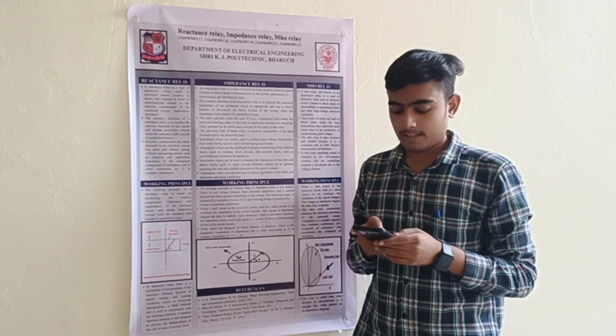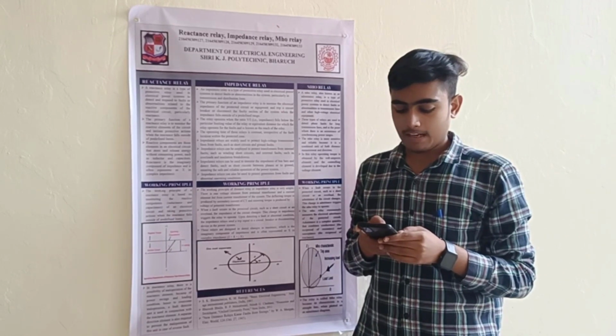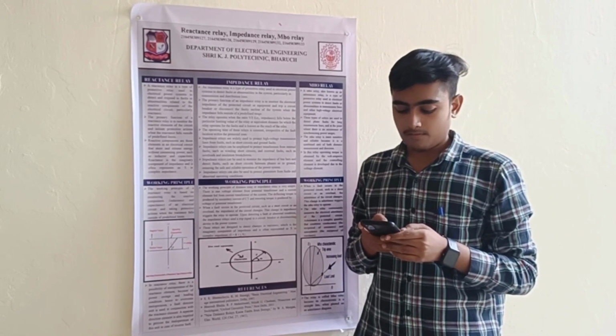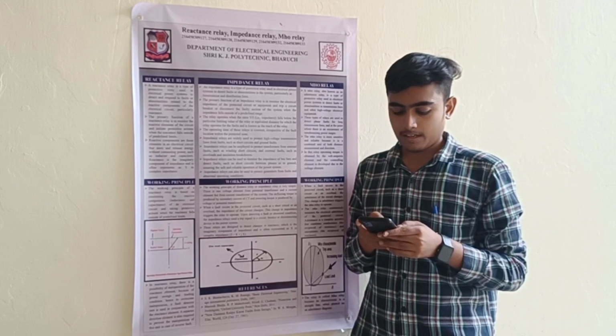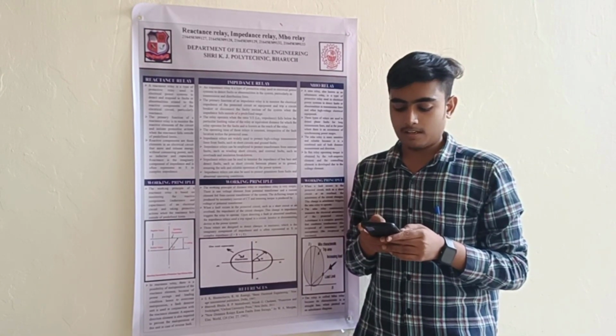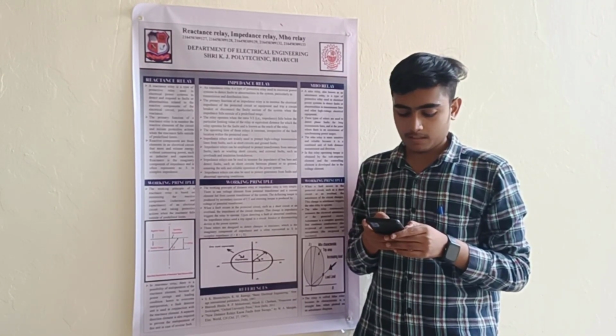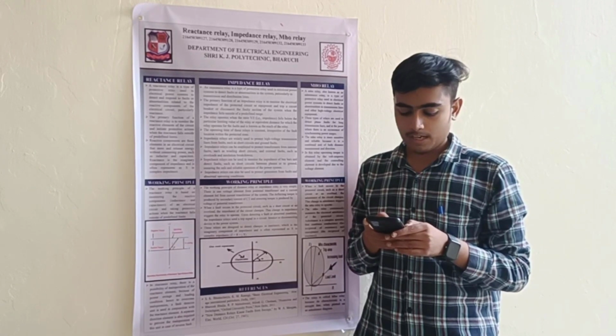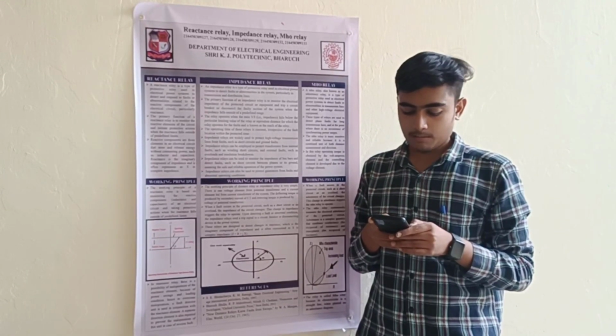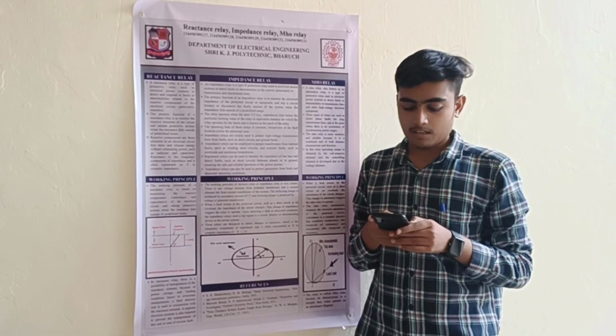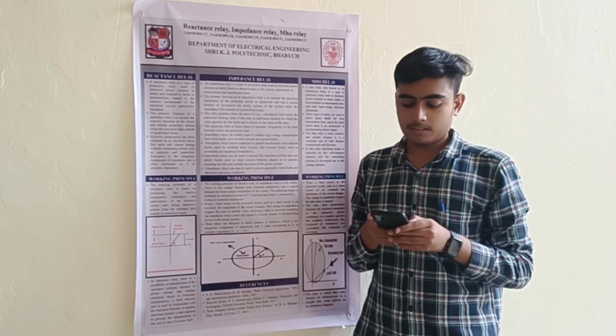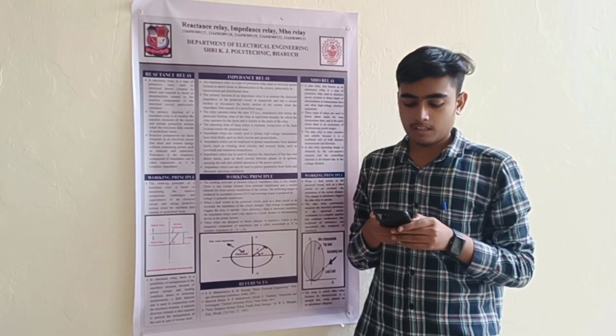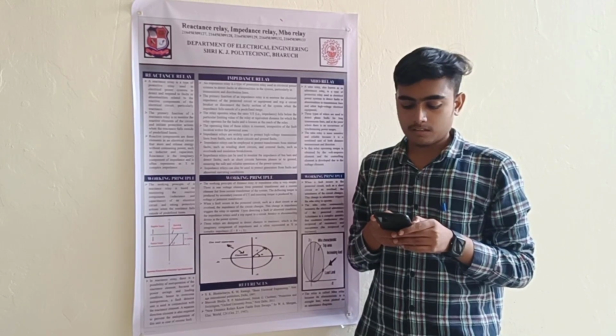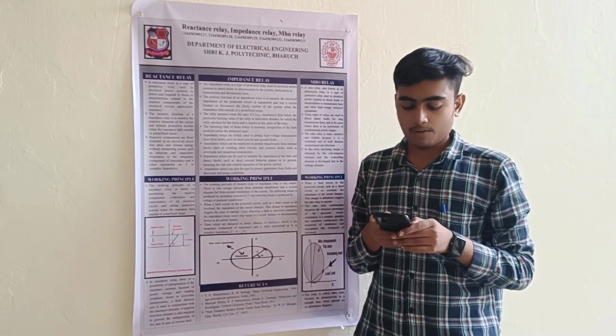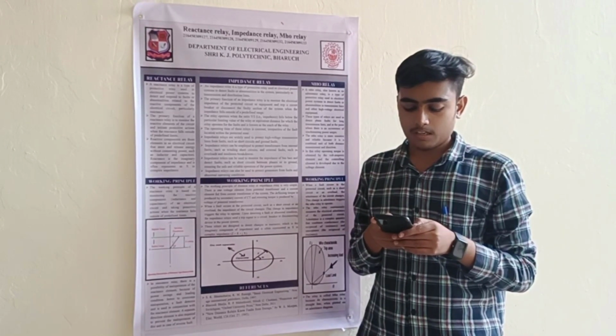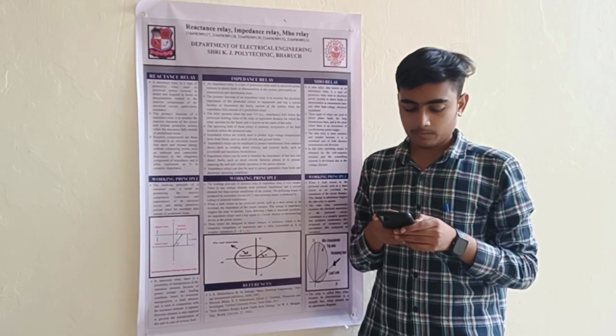Differential protection. Mho relays can be used in a line differential protection scheme where multiple relays are interconnected to protect a transmission line. The relays measure the impedance at both ends of the line and compare them. If there is a significant difference in impedance, indicating a fault, the relays coordinate and initiate the tripping of the circuit breakers at both ends to isolate the fault.